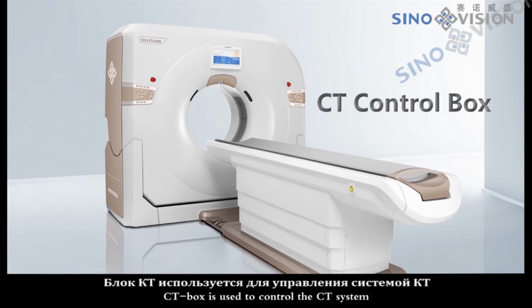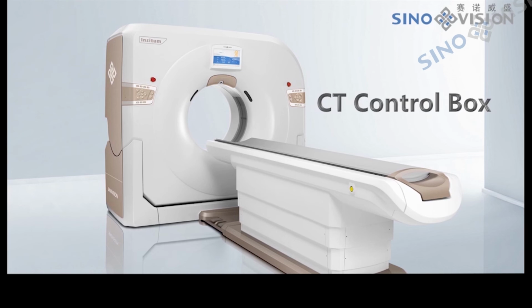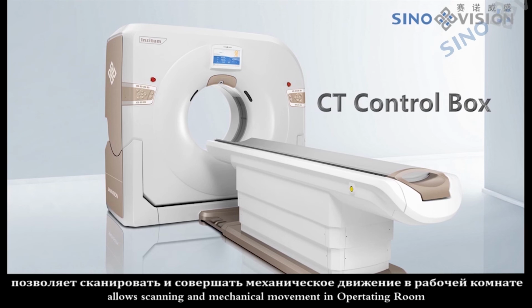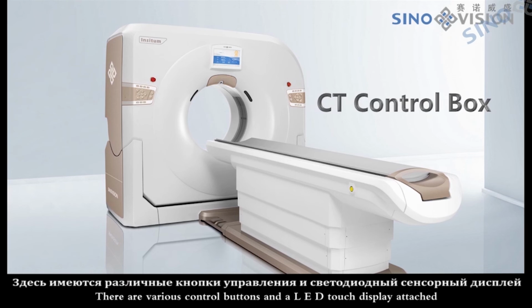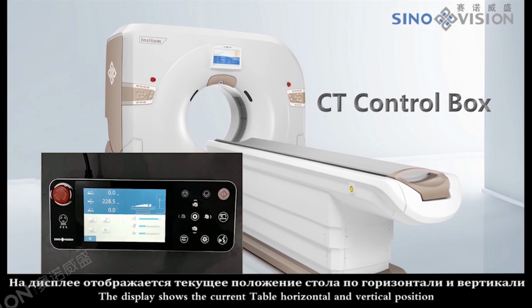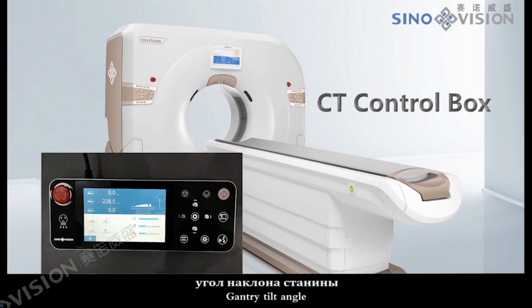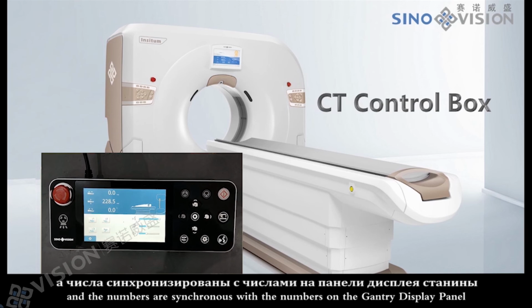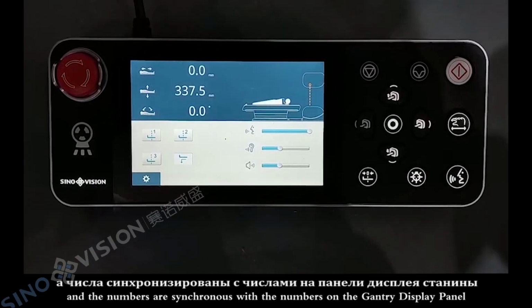CT box is used to control the CT system. Allows scanning and mechanical movement in operating room. There are various control buttons and a LED touch display attached. The display shows the current table horizontal and vertical position, gantry tilt angle, and the numbers are synchronous with the numbers on the gantry display panel.